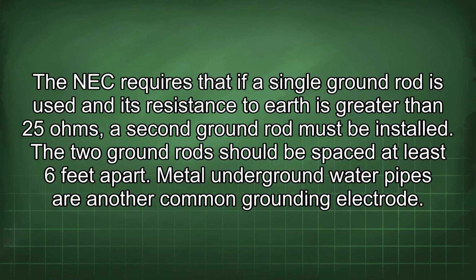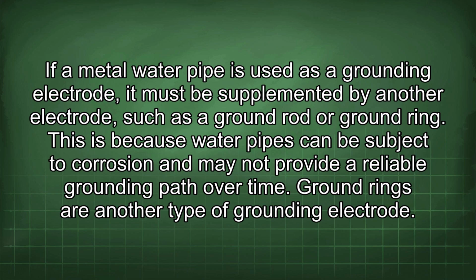Metal underground water pipes are another common grounding electrode. If a metal water pipe is used as a grounding electrode, it must be supplemented by another electrode, such as a ground rod or ground ring. This is because water pipes can be subject to corrosion and may not provide a reliable grounding path over time.